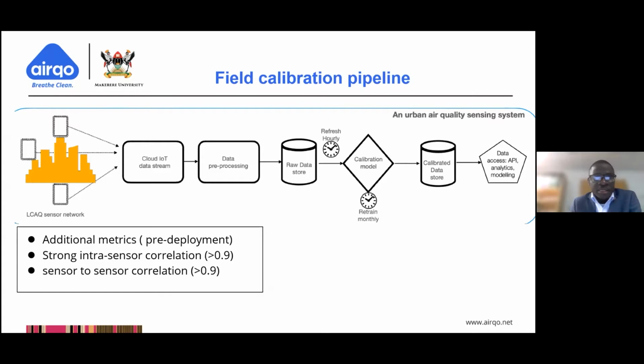And this is what our field calibration pipeline looks like. It's important to mention that we develop our own monitors at the university, and the quality control starts right at the university, where we have some metrics before deployment. Before a device goes for deployment, we do some laboratory co-location, where we monitor the intra-sensor correlation. Each AirQo monitor has two sensors for each parameter. So for PM2.5, we have sensor 1 and 2 as a way of monitoring performance. If sensor 1 and 2 do not exactly agree, it means there's a problem. So we use that as a flag for any corrective measures to be taken. So before deploying, we have these metrics in place, and we also check that the devices agree with each other before taking them to the field.